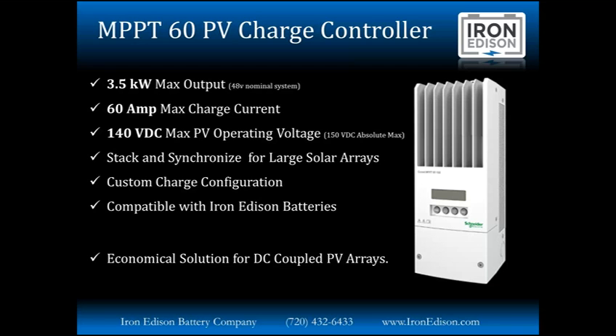This particular charge controller is capable of 3.5 kilowatts of maximum output in a 48-volt system. This equates to 60 amps DC of charge current going into the battery. The maximum DC input for this particular unit is right at the industry standard of 140 to 150 volts DC max. We'll see another unit here in a moment that has an even higher input if necessary. We are able to stack and synchronize dozens of charge controllers to meet, again, specific applications. We've used systems with 6 to 8 charge controllers out of our shop, and it's possible to use even more using some special configurations that we get from Schneider Electric.